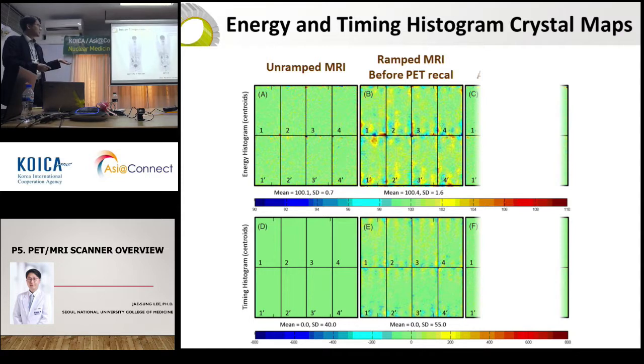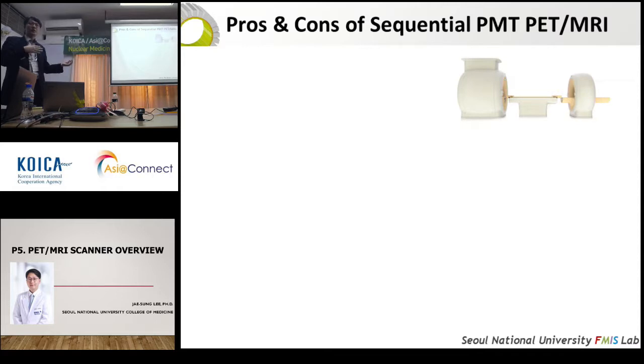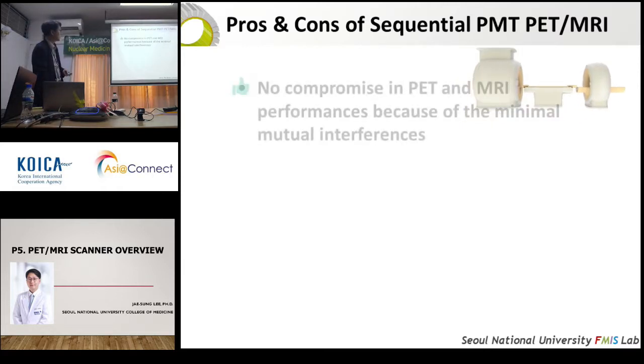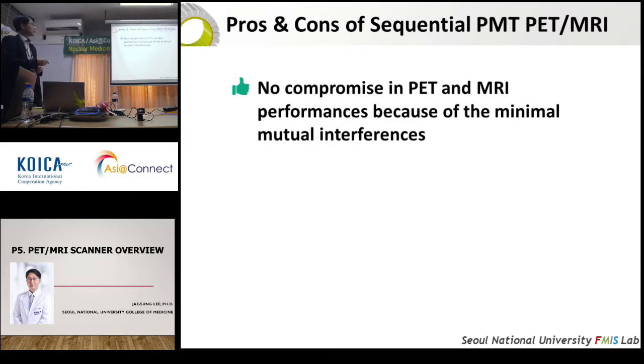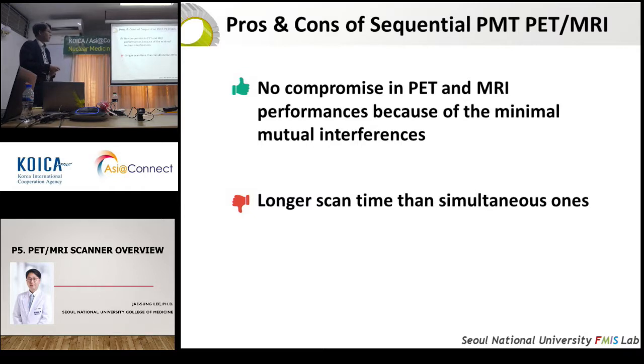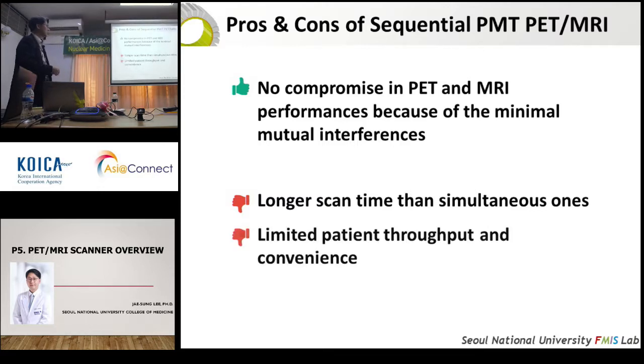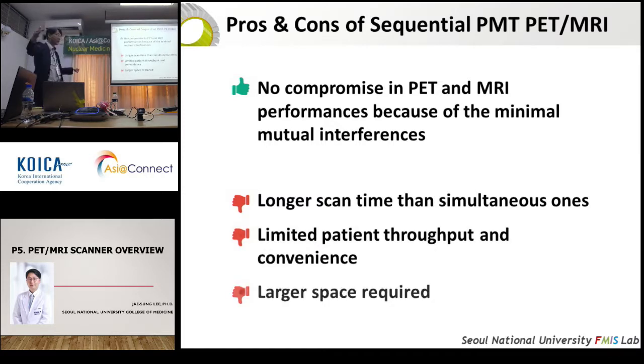Actually, the shielding of the photomultiplier tubes and PET gantry systems went quite well. You can see that the fringe magnetic field of the MRI was less than 2 Gauss or so. Let me skip this part. By the way, because they used their standard time of flight PET system, they could achieve almost the same image quality. These are the PET images from their PET-CT and their PET MRI, and they have equivalent image quality results.